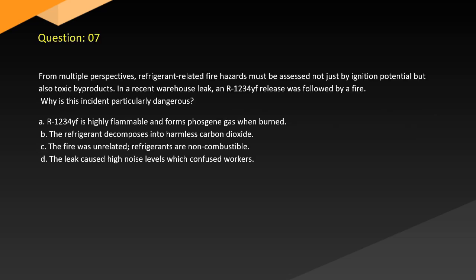Question 7. From multiple perspectives, refrigerant-related fire hazards must be assessed not just by ignition potential but also toxic byproducts. In a recent warehouse leak, an R1234yf release was followed by a fire. Why is this incident particularly dangerous? A. R1234yf is highly flammable and forms phosgene gas when burned. B. The refrigerant decomposes into harmless carbon dioxide. C. The fire was unrelated; the refrigerants are non-combustible. D. The leak caused high noise levels which confused workers.